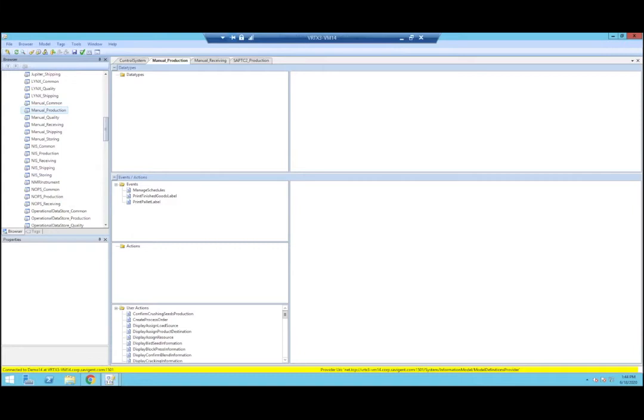Mm-hmm. Yeah. So typically that would be created as an event. So you might have a model that is intended for this piece of equipment. And what you could do is create an event that's called machine state change. And perhaps you created an enumeration as a data type, and you can say running, aborted, idle, some examples. And then inside of the engine, when you're connecting to that piece of equipment, you'll bind the different tool states to the actual equipment. So as it changes those states, those events will be fired. Those could trigger workflows, or if there's a workflow that's paused waiting for this tool state to change, then it could resume.